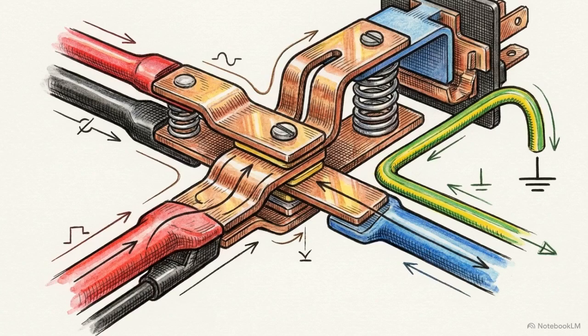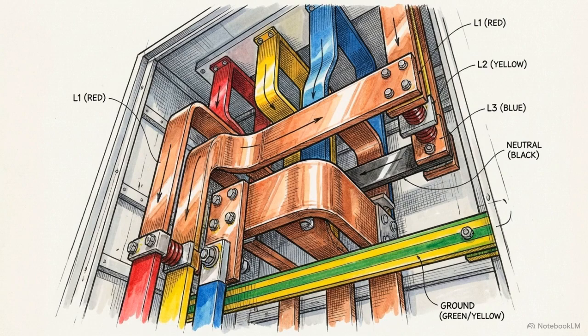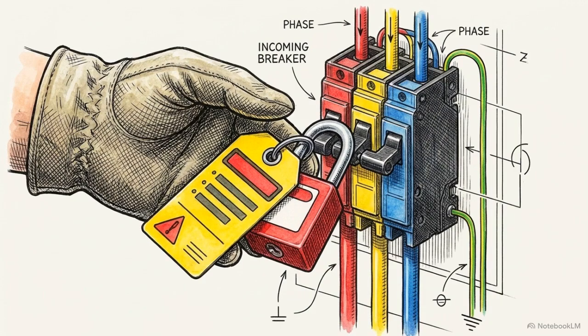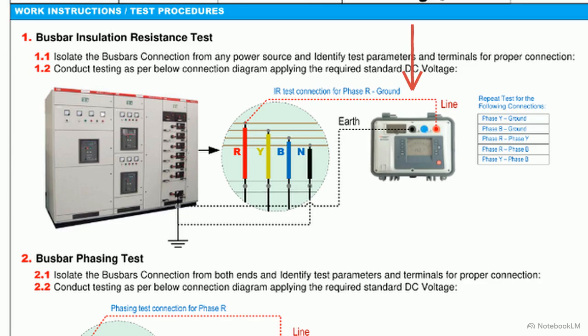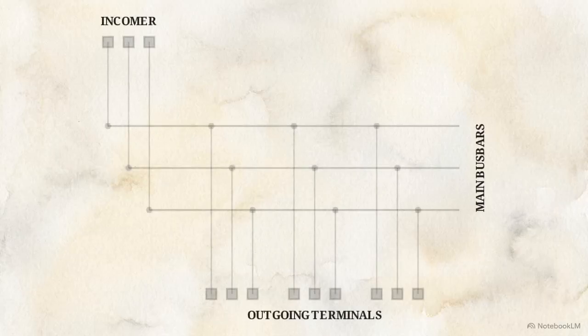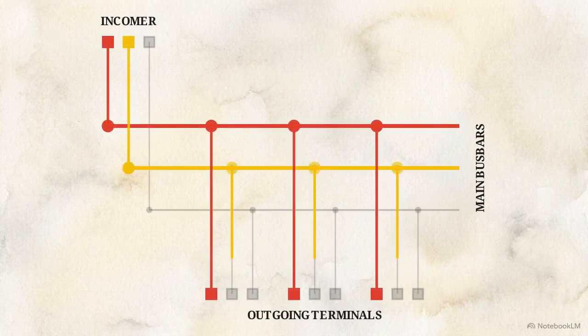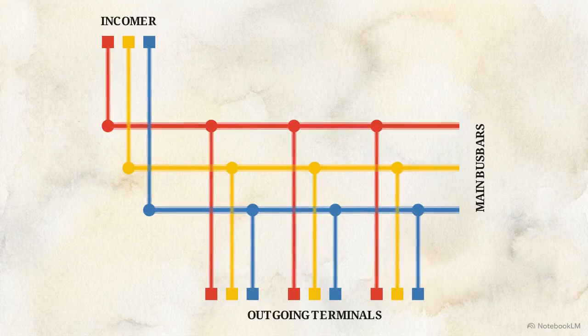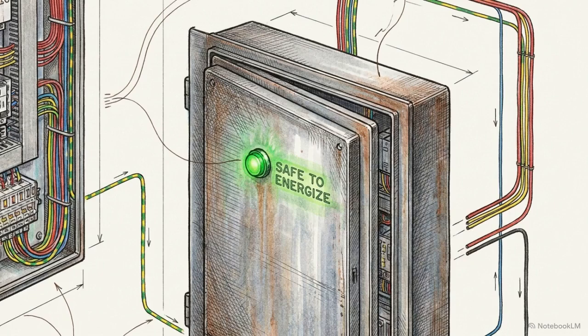Zooming out, we evaluate the board's primary busbars, the massive conductive elements that carry the full operational load. Before applying high test voltages, the busbars must be isolated from all potential backfeeds, capacitors, and outgoing electrical loads. Engineers use an insulation resistance tester to apply a standard DC voltage, measuring resistance phase to ground and phase to phase across the busbars. This introduces a lethal capacitance hazard, requiring the engineer to physically ground and completely discharge every tested busbar immediately afterward. Finally, they execute point-to-point phase continuity checks, tracing the correct phasing reference from the incomer section all the way through to the outgoing terminals. Proven, mathematically verified busbar insulation is the absolute prerequisite before live grid voltage can enter the system.